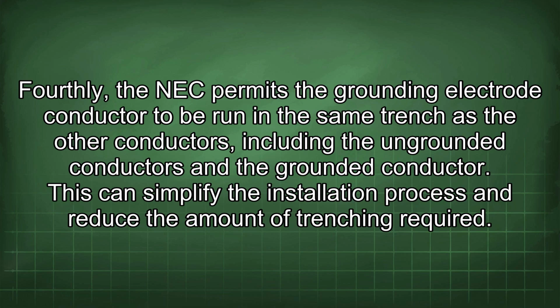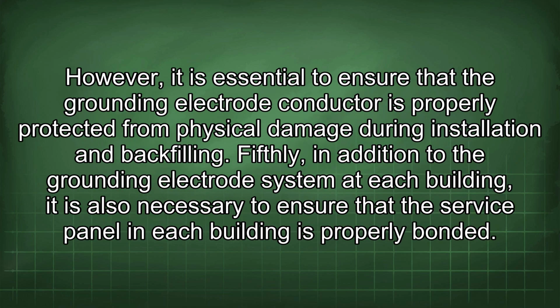Fourthly, the NEC permits the grounding electrode conductor to be run in the same trench as the other conductors, including the ungrounded conductors and the grounded conductor. This can simplify the installation process and reduce the amount of trenching required.